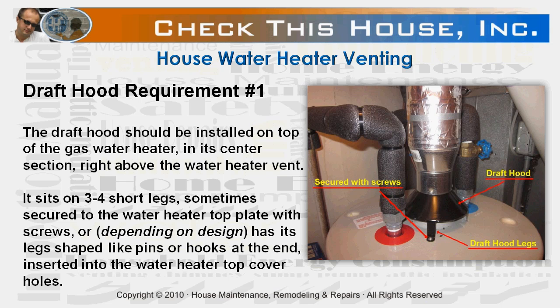There are three basic draft hood requirements. Number one: the draft hood must be installed on top of the gas water heater, in its center section, right above the water heater vent. You can see on the picture that the draft hood sits on three — sometimes four — short legs, which are either secured to the water heater top plate with screws, or, depending on the design of your appliance, has its legs shaped like pins or hooks at the end, which are inserted into the water heater top cover holes.